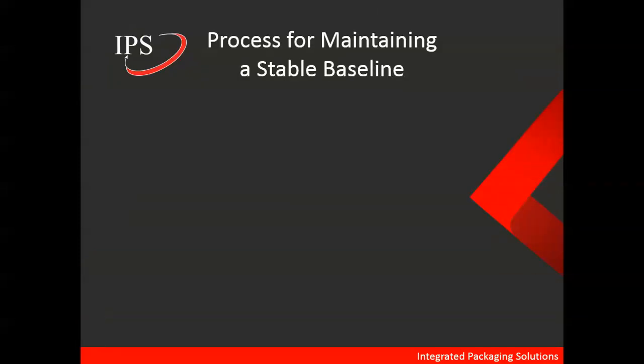So we talked about baseline before, and we talked about the process for maintaining a baseline. Most plants know exactly how to calibrate their gauges, so calibration is something that every plant is going to do. However, a lot of plants don't realize that there is a need to validate after they calibrate. What that means is that there can be a bad calibration, and unless you have a mechanism to identify whether the calibration is good or bad, you may measure tooling with bad values until the machine is calibrated again. And so the validation process assures that your calibration is good.